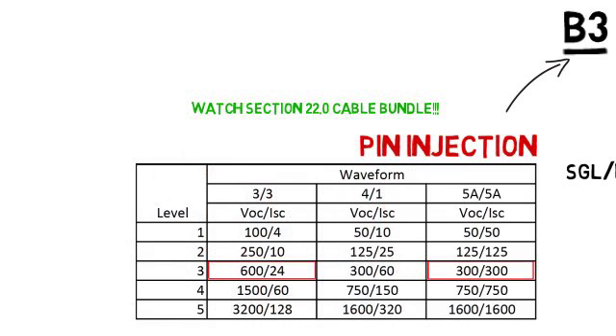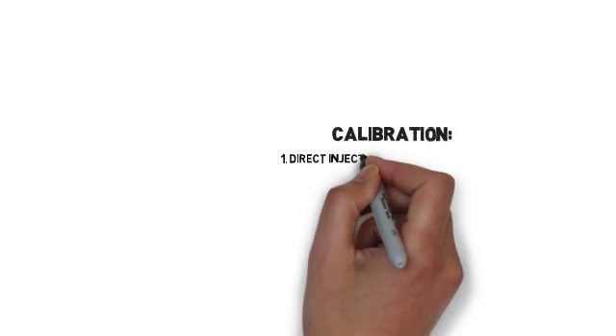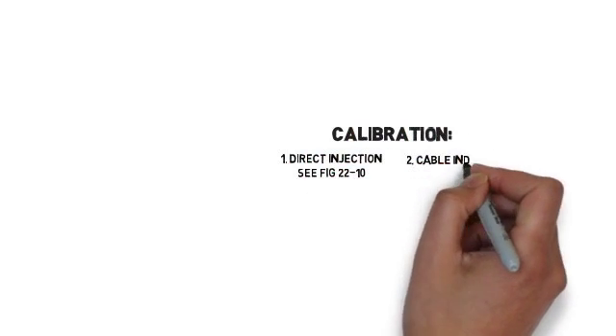Now that we've got the test levels and waveforms nailed down, let's talk about the calibration. Typically, there's one of two methods used: direct injection, where the power is applied directly to the line under test, or cable induction method.